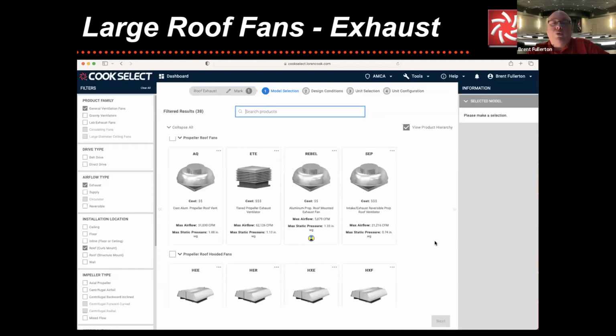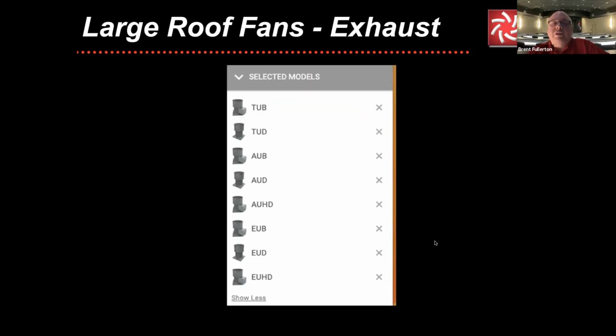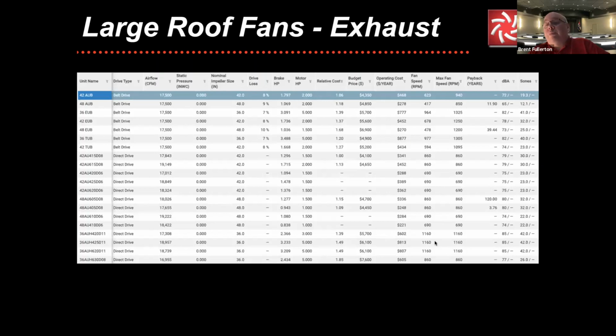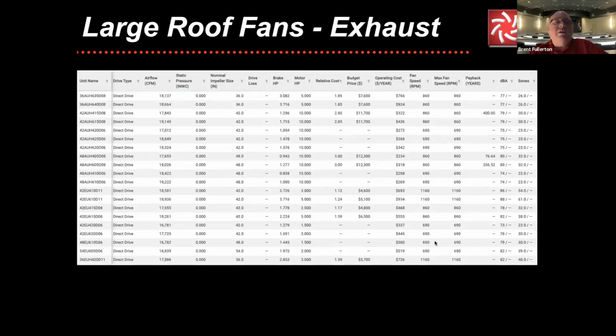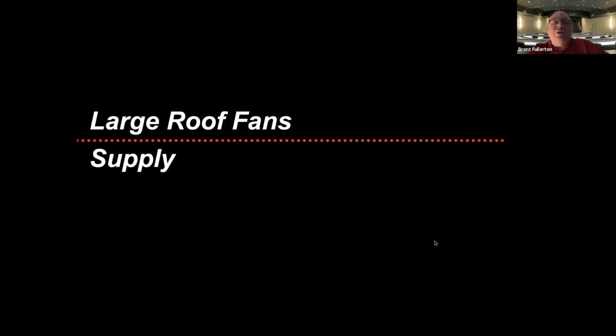Now let's go back and look at some more different styles of products. Once again, we're still in the exhaust mode. So taking a look at all of these legacy styles of products, we can get a wide range of selection, whether belt drive or direct drive. Now, when they're direct drive, the motor cannot be easily serviced from outside the roof. You have to actually take the product off the roof curb, or you have to get like a cherry picker from below. So once again, there are pros to a belt-driven fan. There are pros to a direct-driven fan. Likewise, there are cons to each style of product.